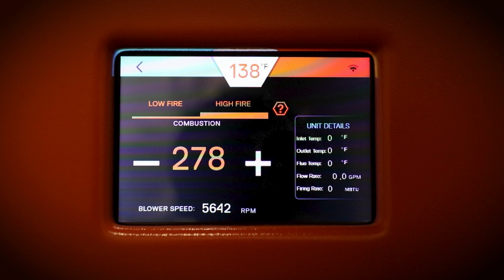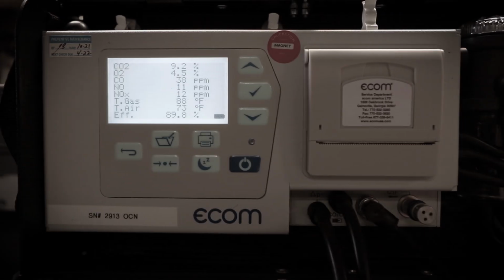When the CO2 and CO values have settled in the acceptable range for at least 2 minutes, you can enter low fire by pressing low fire on the display screen. Allow the unit to enter low fire. For low fire, the CO2 needs to be between 9.1 and 9.3% on natural gas units. On propane units, the CO2 needs to be between 10.1 and 10.5%. Additionally, make sure the CO level is less than 60 parts per million.